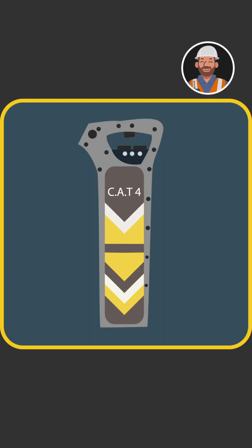Using a CAT scanner. CAT scanners offer 4 modes of operation. Avoidance mode. Start with this for an initial sweep of the area. Follow with detailed scans using other modes, for example, CAT 4+. Power mode, P, detects live cables with current flowing through them.